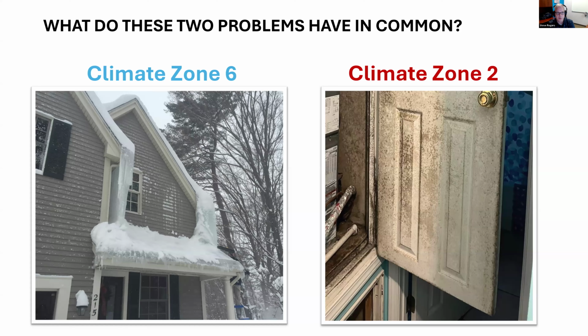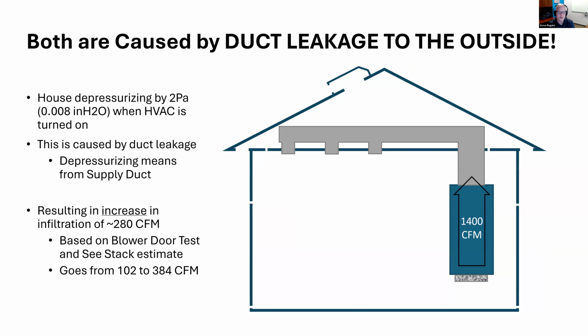But the result of what they cause is completely different because of the climate and because of the way that the system is put together. And the thing that they have in common is duct leakage to the outside of the house. So anytime ducts are not completely inside of conditioned space, we can have a problem that we call duct leakage to the outside, or duct leakage outside of the conditioned envelope.